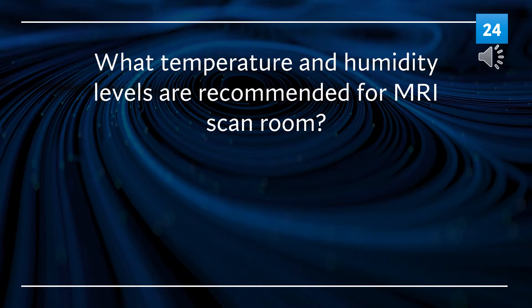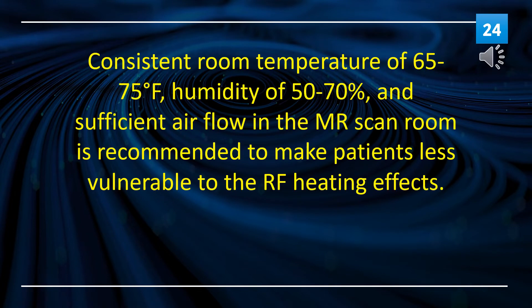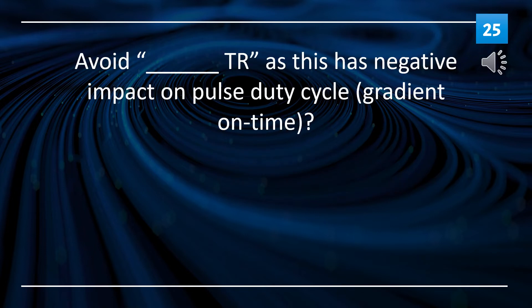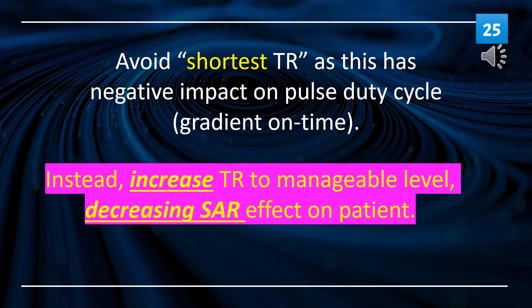What temperature and humidity levels are recommended for the MRI scan room? A consistent room temperature of 65 to 75 degrees Fahrenheit, a humidity level of 50 to 70%, and sufficient airflow are recommended to make patients less vulnerable to RF heating effects. Avoid the shortest TR, as this has a negative impact on the pulse duty cycle; instead, increase TR to a manageable level to decrease SAR effect on the patient.